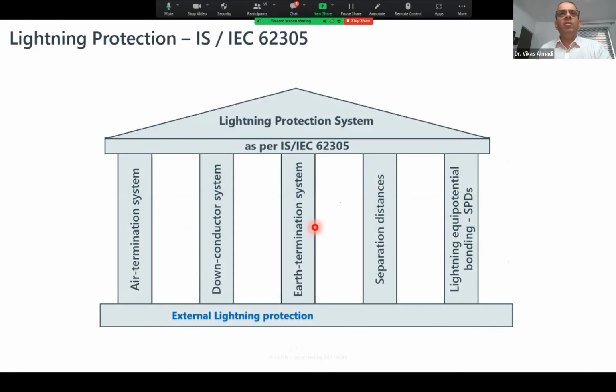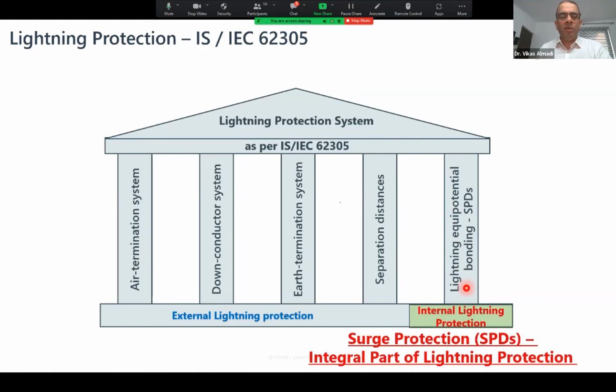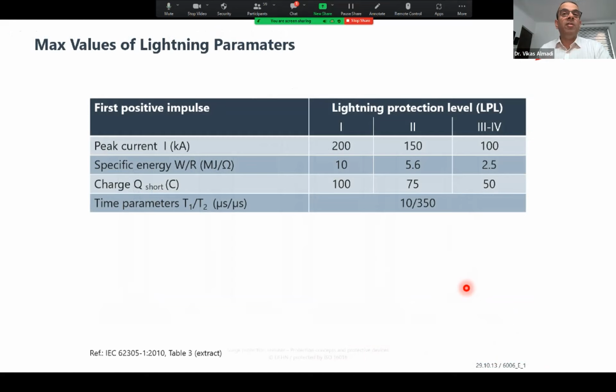So when we talk about the bigger subject of lightning protection, surge protection is a part of it. That's why I'm showing these standards to you. Without surge protection, even lightning protection cannot take place. So this is an important part, and it cannot be omitted. Whereas when we talk about lightning, we are talking about very high currents of up to 200 kiloamperes in class 1 or up to 100 kiloampere in class 3 and class 4. Again, when I talk about lightning, automatically I talk about this wave shape 10 by 350, which is known as impulse. So the difference between lightning and surge is 10 by 350 and 8 by 20. Lightning means impulse, surge means overvoltage in the surge protection category.